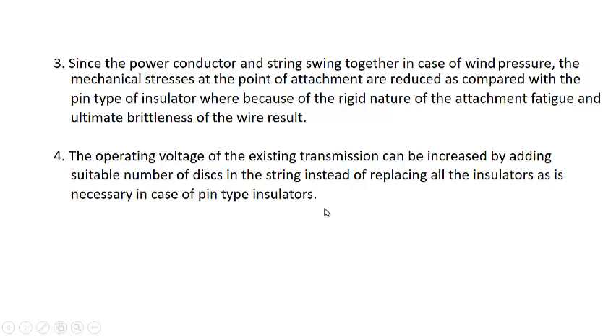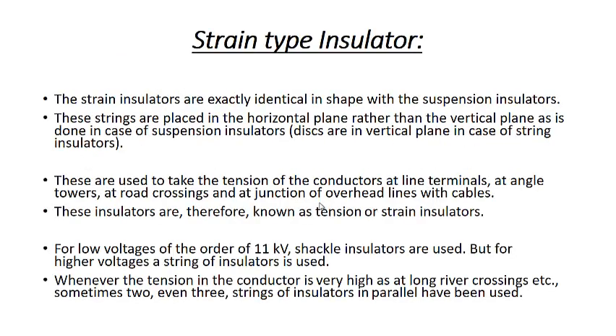For example, if you have to go from 11 kV to 33 kV, you just have to use two more discs, rather than replacing the 11 kV pin type insulator by a 33 kV insulator. So this is one more advantage of it.